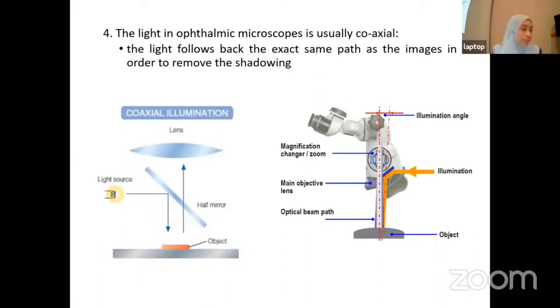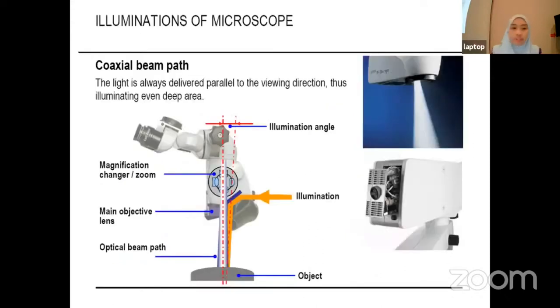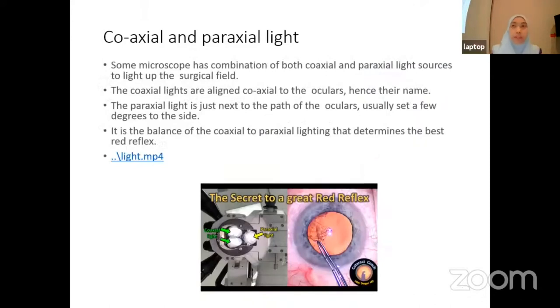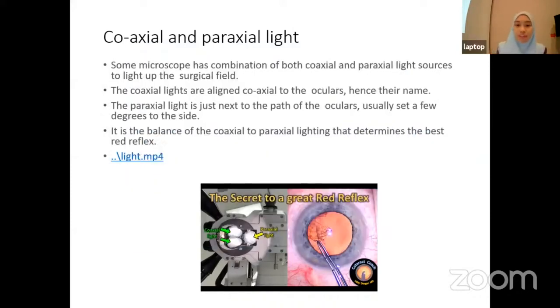The light in the microscope is usually coaxial, meaning the light follows back the exact same path as the image in order to remove shadowing. As shown in the photo, the light is delivered parallel to the viewing direction, so it can illuminate even the deep areas. Some microscopes also have a combination of both coaxial and paraaxial light sources to light up the surgical field. The coaxial light is aligned coaxial to the optical axis, and the paraaxial light is positioned just next to it — usually set a few degrees to the side. It is the balance of coaxial and paraaxial lighting that determines the best red reflex.